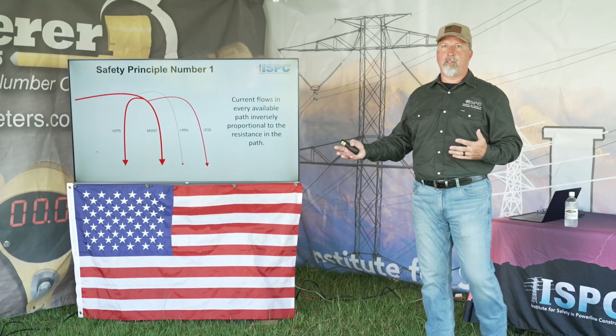Safety principle number 2: if you insert a resistance into a current carrying grounded conductor, a voltage rise will appear. At the top there, we have an open point at 7,200 volts — put a meter across that, it's open, no resistance, you're going to measure 7,200 volts to ground. In the second depiction, you're going to have something less than 7,200 volts, because we've inserted a resistance — whether that's a dirty connection, a not properly closed disconnect, or you.